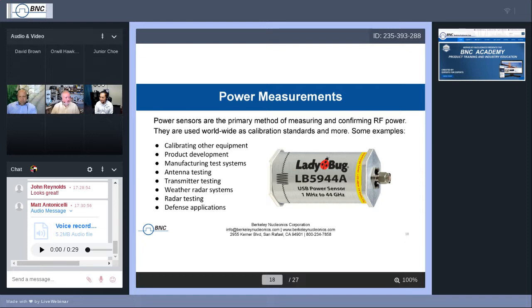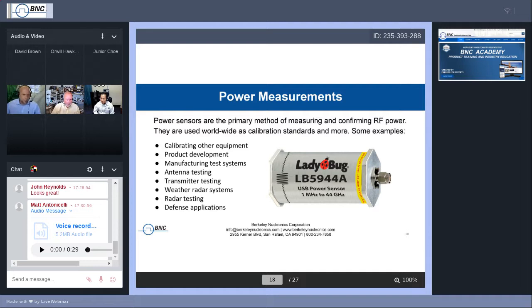Thank you, Junior. That was very interesting. Before I get into our power sensors, I've really enjoyed using these Berkeley Nucleonics sources — it's nice to have the front panel similar to the GUI on the software; it makes my demonstrations very easy. We make power sensors for all different kinds of applications, but as a general rule, power sensors are used as primary standards around the world for measuring power. Here's a list of typical uses: calibrating other equipment such as network analyzers and sources; product development — you can't reliably know your device's output power without an instrument to measure it; and manufacturing test systems, used at the end of the production line to make sure devices don't transmit out of spec.